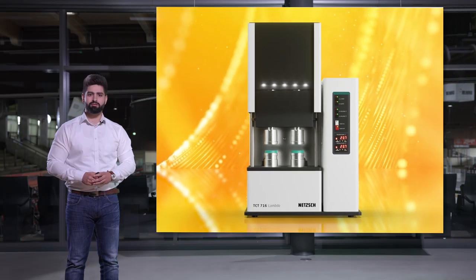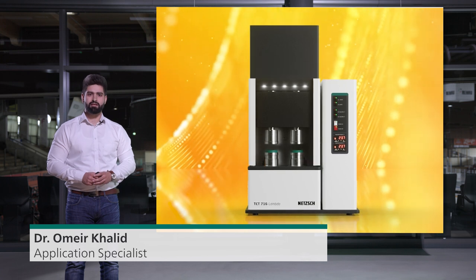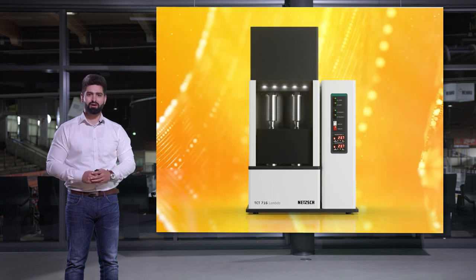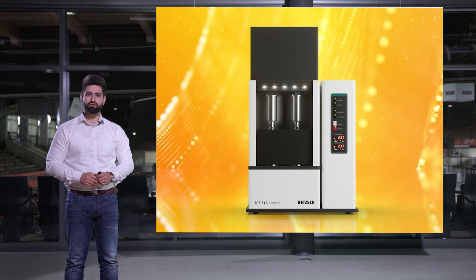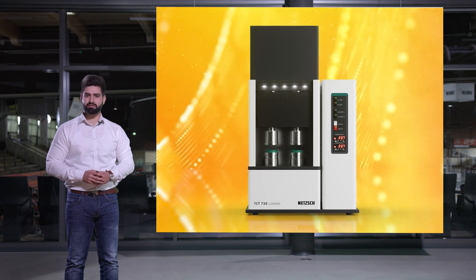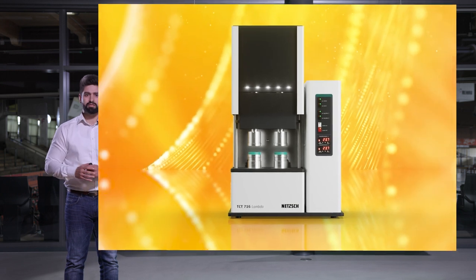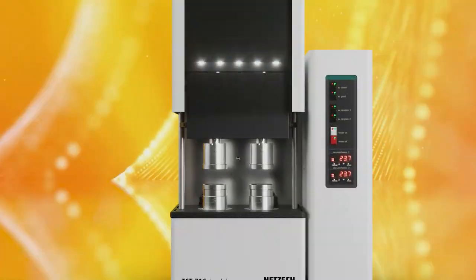Now we would like to present a new member in our family of thermal conductivity testers, broadening our product portfolio for thermophysical properties to always have the right solution for your application. We introduce our first guarded heat flow meter for highly accurate determination of thermal resistance for medium conductive samples in the temperature range from minus 10 degrees up to 300 degrees Celsius. Please welcome the TCT 716.